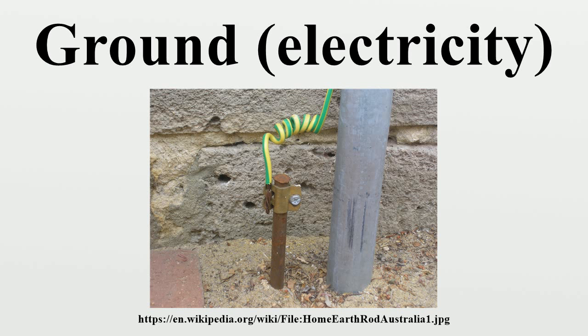This is especially important in bathrooms, where one may be in contact with several different metallic systems, such as supply and drain pipes and appliance frames. The equipment bonding conductor is usually also used as the equipment earthing conductor. A grounding electrode conductor connects one leg of an electrical system to one or more earth electrodes. This is called system grounding, and most systems are required to be grounded.